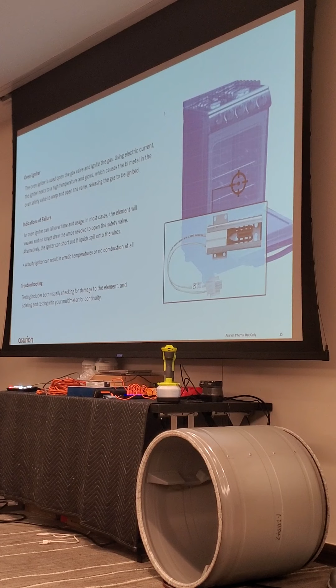Huh? No. The element can. The gas goes on and off, but the igniter stays on, at a lower wattage, but it stays on. Because once you get up to temperature and it needs to reignite to maintain that temperature, it's going to work off the thermostat. So when that gas comes out, it's going to automatically ignite because that igniter never goes off.